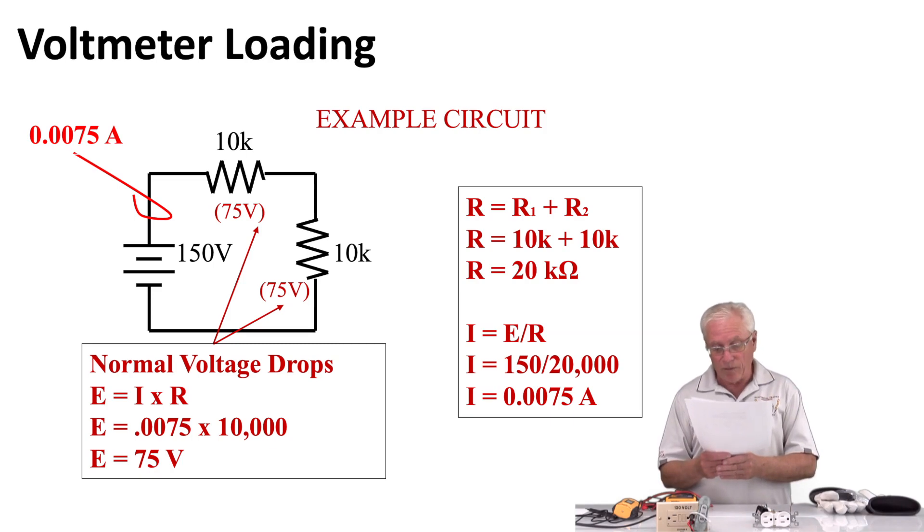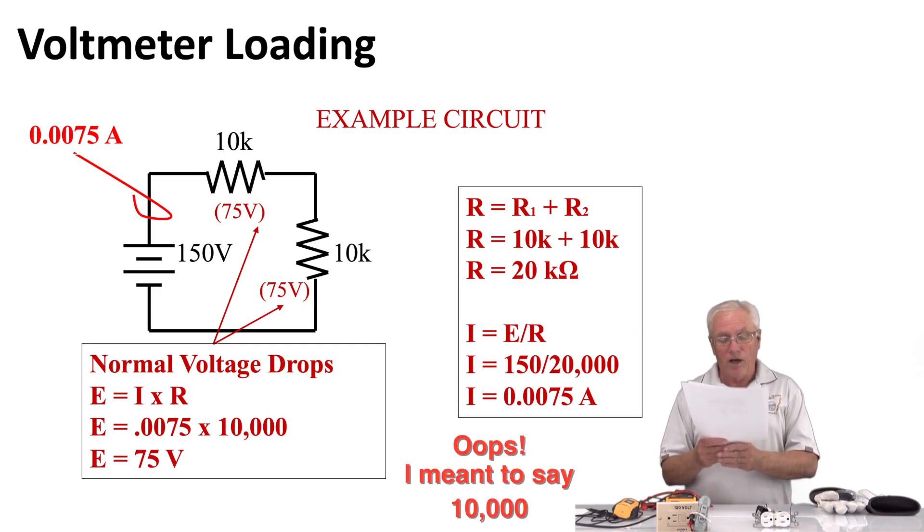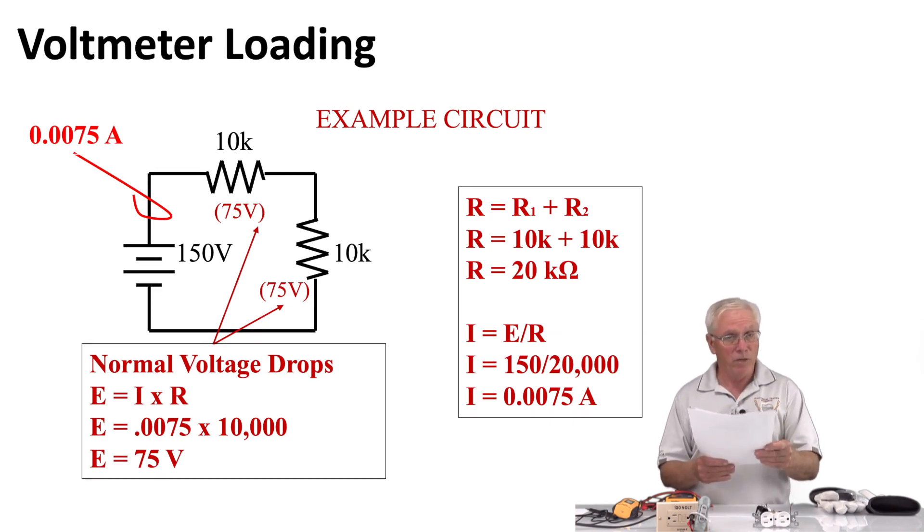Below that, you'll see we want to find the current, we simply divide E divided by R, so 150 volts divided by 20,000 ohms will give us 0.0075 amps, which is basically 7.5 milliamps. We can determine each voltage across the resistor. If we do E equals I times R, if we take 0.0075 times 10,000 at each of these resistors, we should have a voltage drop of 75 volts on each resistor. That will be under normal conditions. In a moment, we'll see what happens when we put a meter on the circuit.